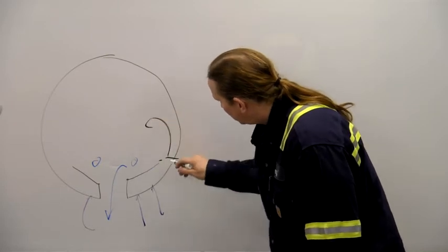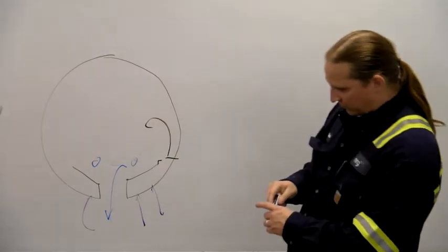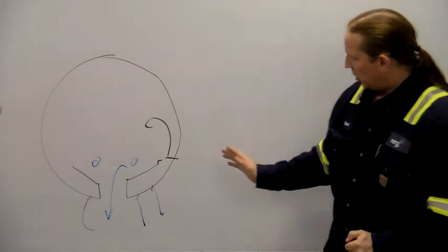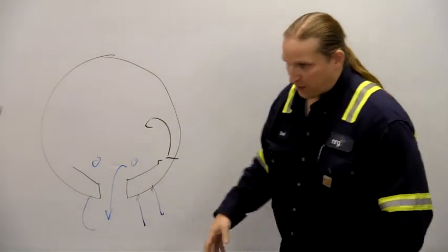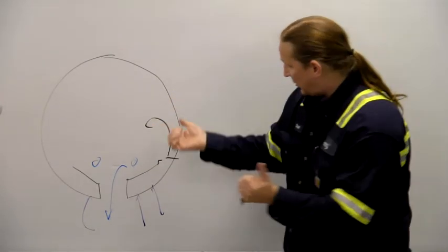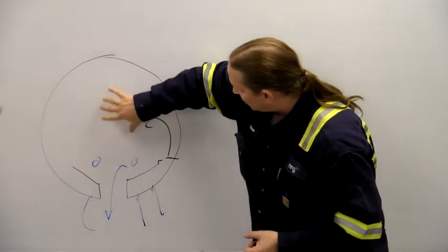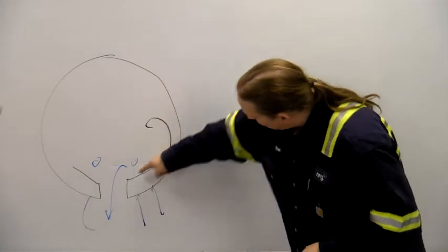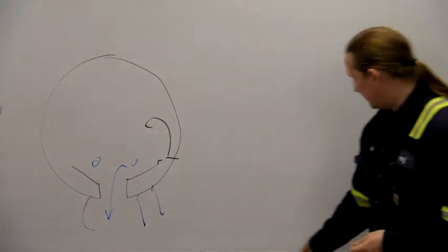So here the wet steam is channeled up and it goes into a cyclone moisture separator. It's got this scoop shape to it and it directs the steam and the water up through it. And then the steam goes out the sides and fills this whole space. And then the water goes down the downcomer and makes another lap.